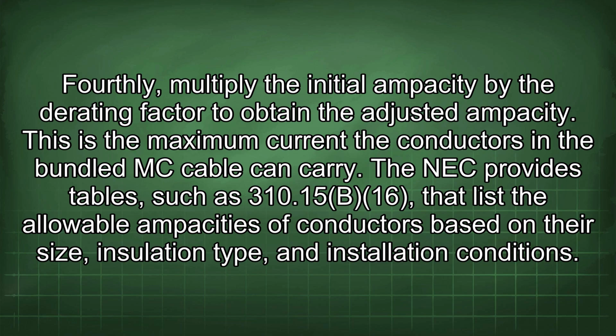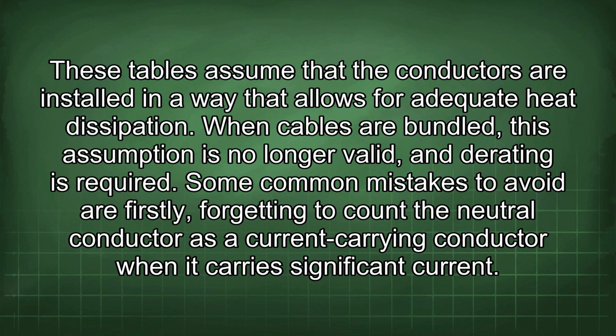The NEC provides tables such as 310.15(B)(16) that list the allowable ampacities of conductors based on their size, insulation type, and installation conditions. These tables assume that the conductors are installed in a way that allows for adequate heat dissipation. When cables are bundled, this assumption is no longer valid and derating is required.